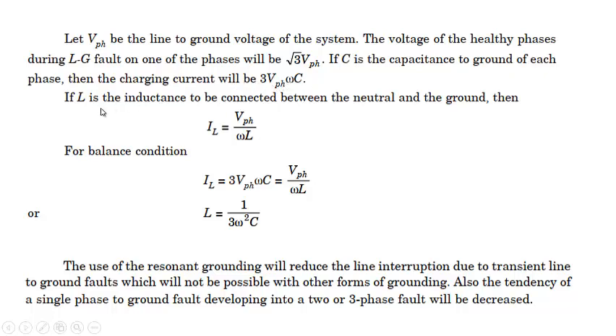And the current flowing through the inductance of the neutral, that's the Petersen coil, will be V phase divided by omega L. So under balance conditions, this current should be equal to this current. That means V phase by omega L should be equal to 3 times V phase omega C. So in this case, L will be equal to 1 by 3 times omega square C.